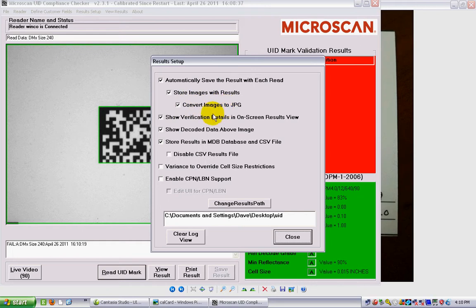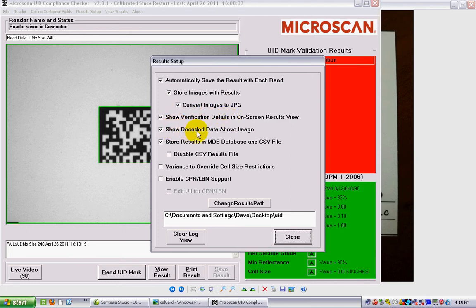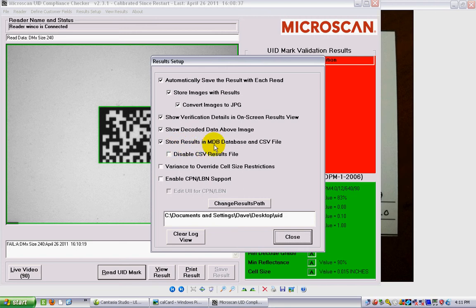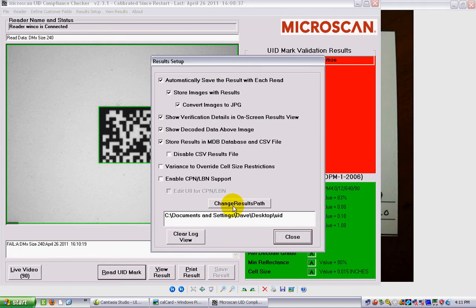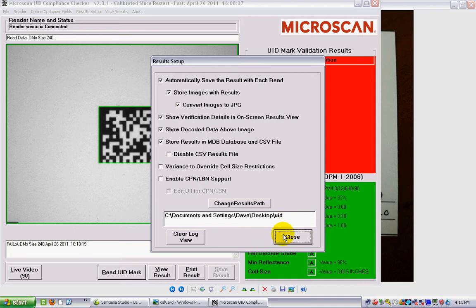I want to see my verification details, so I check off this one. I want to see the decoded data above the image, that's in this area here, so I keep that checked off. I also want to have a database and a CSV file stored along with the results, so I tend to check that one off as well. Had I got a variance to override those cell size restrictions, I would check this box off here. And then the other thing I can do is I can change the results path, the path to the folder where the results are actually stored. You can see in my case I'm just storing them in a folder called UID on my desktop, and that works out fine for me.